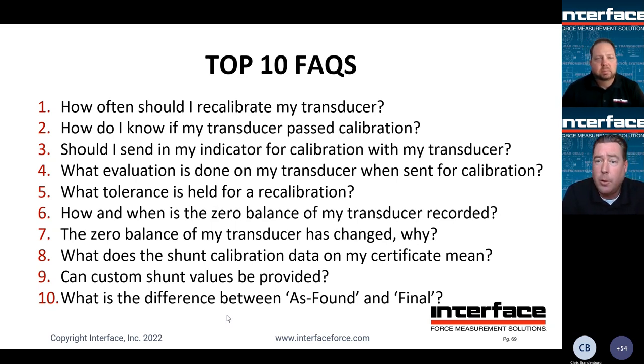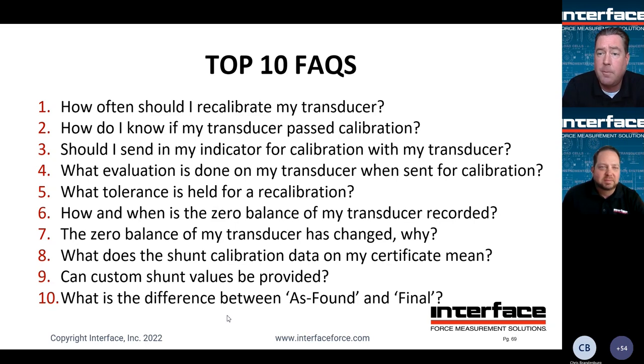All right, so we get a lot of questions from customers. These are kind of the top 10 we put together. I'm sure there are some others that we've not captured in this, but we'll touch on these. A very common question is, how often should I recalibrate my transducer? And that's not for us to say. We can make a recommendation, and typically speaking, we recommend 1 year. That is contingent upon the usage type and criticality of the measurement.